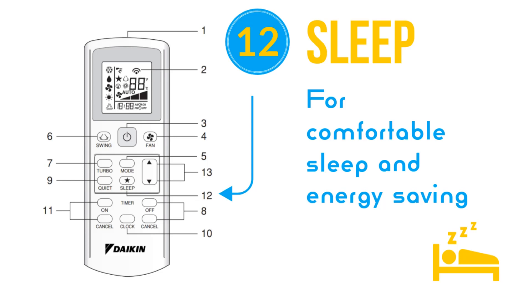Under cooling mode, the set temperature is increased by 0.5 degrees Celsius after the first half hour, another 0.5 degrees Celsius after the second half hour, and 1 degree Celsius after the following 1 hour. Under heat mode, the set temperature is decreased by 1 degree Celsius after the first half hour, another 1 degree Celsius after the second half hour, and 1 degree Celsius after the following 1 hour.